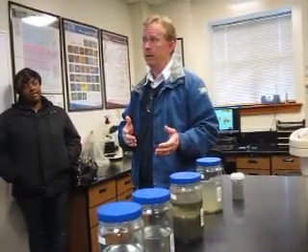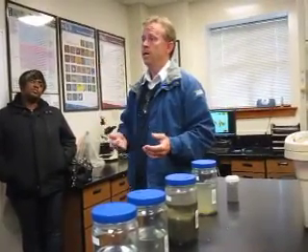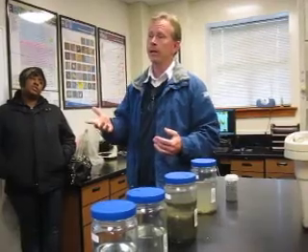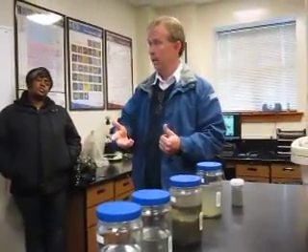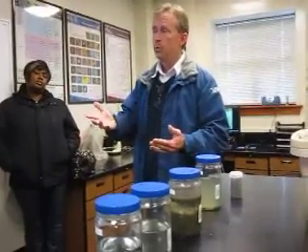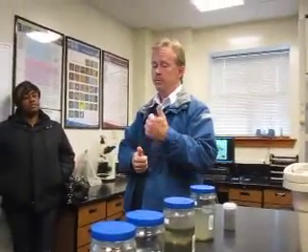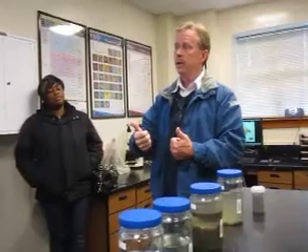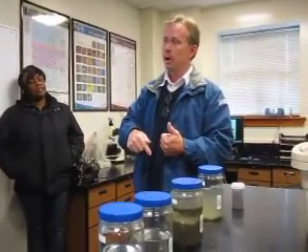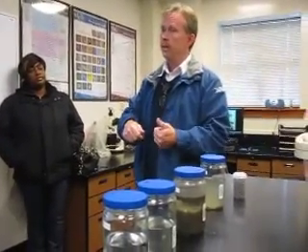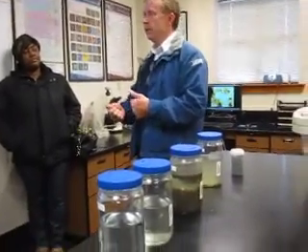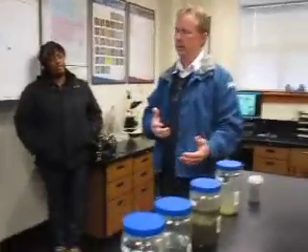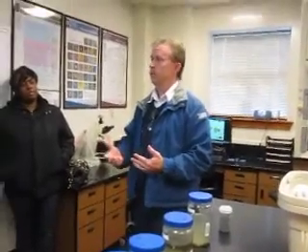If they see something like the phosphorus going up, then that operator will start up the ferric feed. And then once he starts the ferric feed, he's watching his alkalinity. He's always watching it, but now he's really watching it. If his alkalinity starts dropping off and hits 70 or lower, he's going to start up the sodium hydroxide. So those operators are always collecting samples and making process control adjustments.